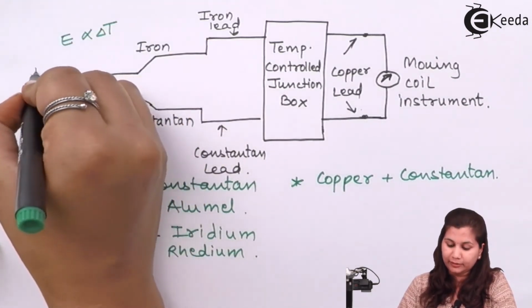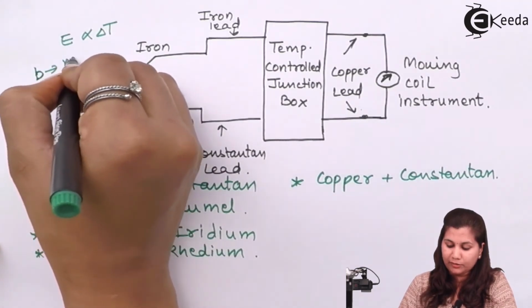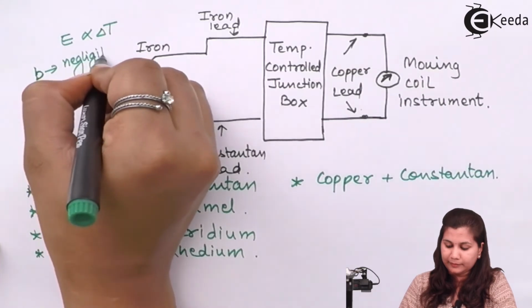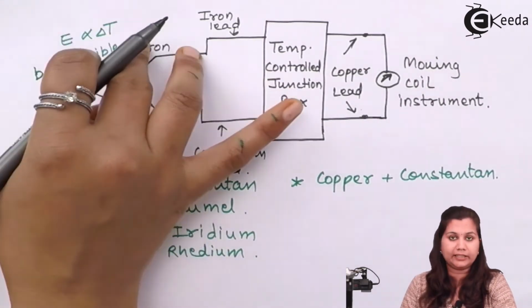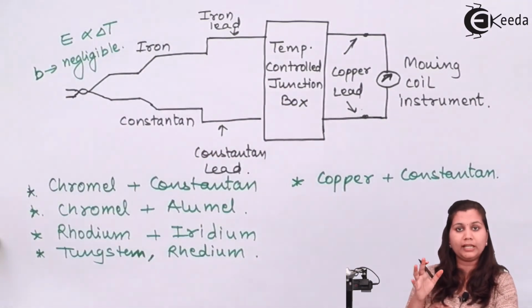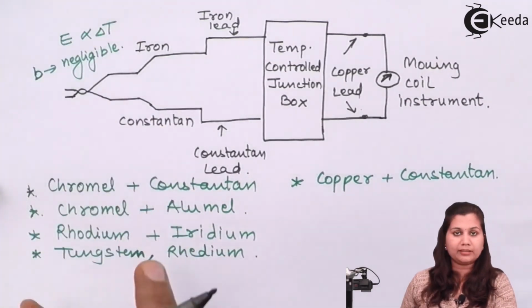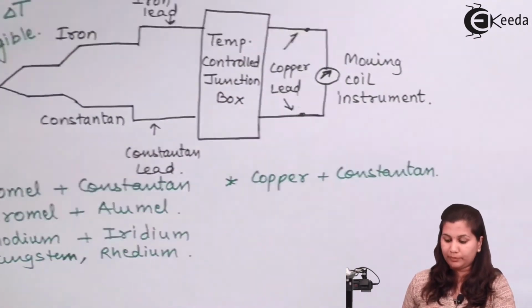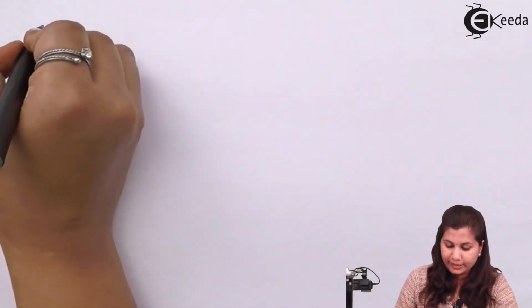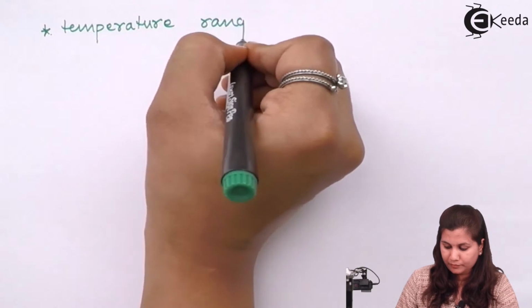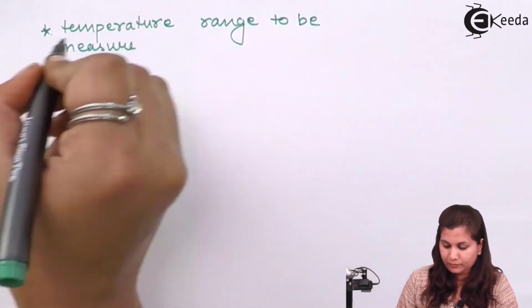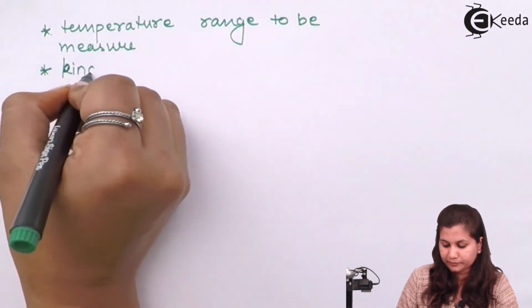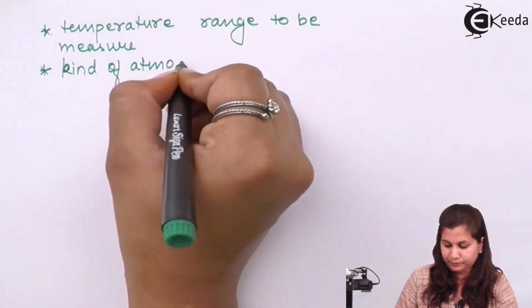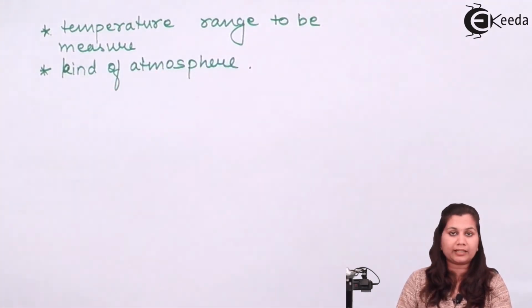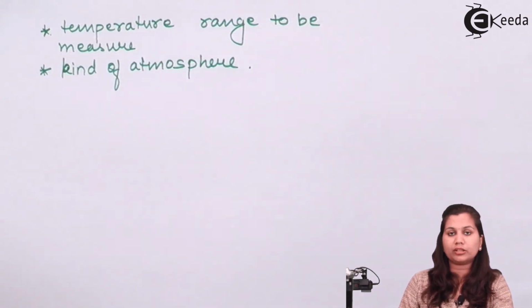Now as I've said, to get a linear relationship between the EMF generated and the temperature difference, the B constant should be very small and can be neglected, and there should be only the linear relationship. The quadratic relationship should be neglected. In that way the metals have to be chosen. Also, the metals are chosen depending upon the temperature range which we want to measure, and also the kind of atmosphere. So these are the factors which affect the choice of the metals.